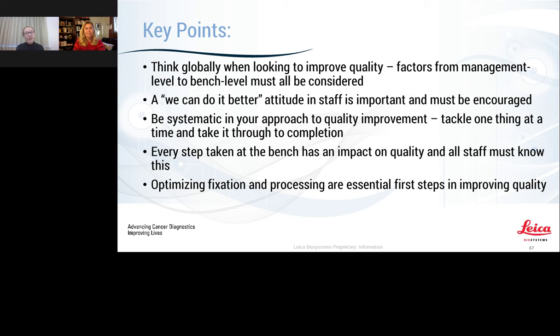Okay, so the first thing, rodent tissue is dry and brittle sometimes. 12 hours is a very long protocol for the size of tissue, and I would recommend optimising that tissue protocol. Many tissue processors nowadays are very efficient compared to some of the older dip and dunk with no heat, no vacuum, no agitation.